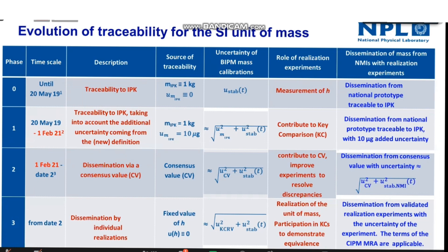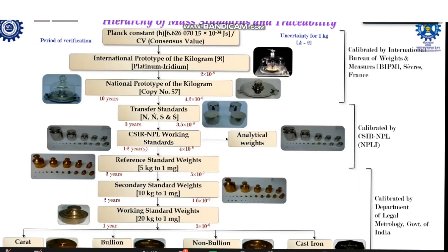I will show you the new certificate which we have received very recently. This is how we are presently working at the apex level. Looking at the same traceability chart shown before, nothing has changed from the NPK down to the commercial weights; however, at the top we find that traceability has now started coming from the consensus value.